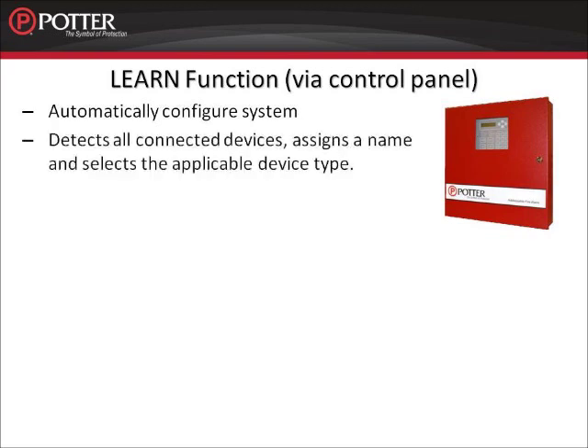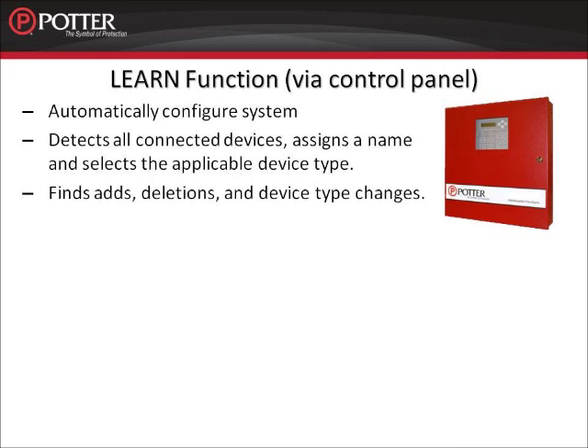The LEARN function detects all connected devices, assigns a name, and selects the applicable device type, whether it's a module, a sensor, or a PLINK device. The LEARN function will also determine if there have been any device type changes, such as changing a smoke to a heat detector. It will also determine if there have been any devices removed from the system. If running the LEARN function after the initial startup to add or remove devices, no existing programming is lost.